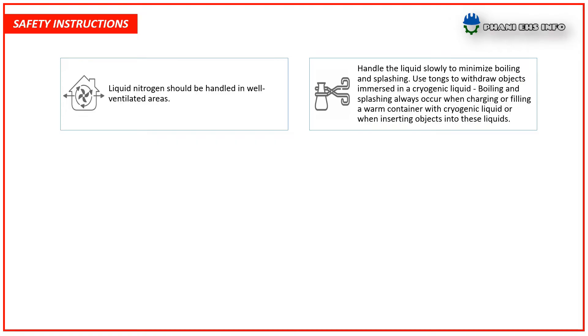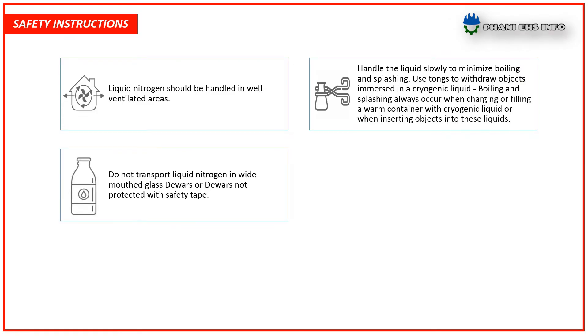Boiling and splashing always occur when charging or filling a warm container with cryogenic liquid, or when inserting objects into these liquids. Do not transport liquid nitrogen in wide-mouth glass dewars that are not protected with safety tape.